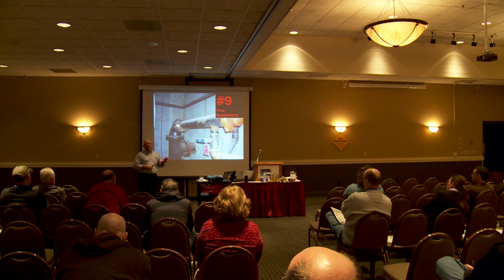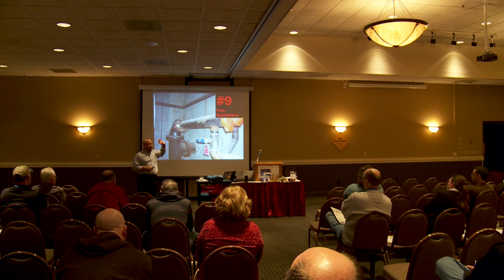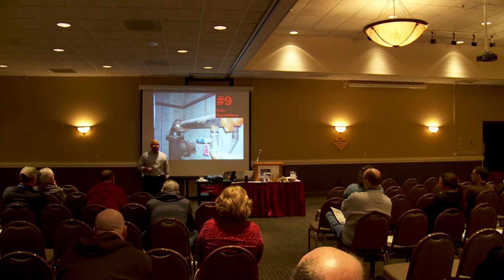So a good survey will document the appropriate backflow preventer, or like in some old buildings that we surveyed, there's no backflow preventer installed on really old buildings. So that water's just sitting in there, growing and rusting, and every time you have a pressure fluctuation, flush or main break, guess what happens when that hiccups? It pulls that water into the supply. People say, oh, I got rusty water for a couple hours, then it went away. Sound familiar?